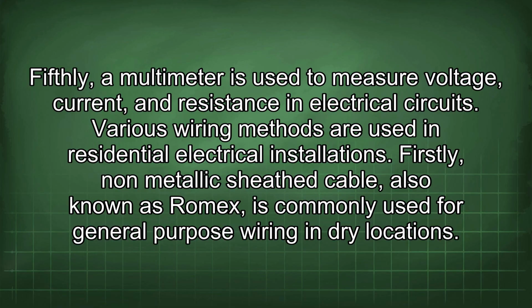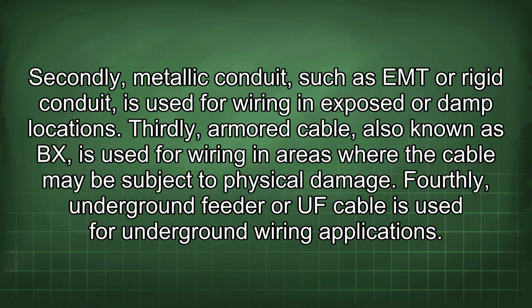Firstly, non-metallic sheath cable, also known as Romex, is commonly used for general purpose wiring in dry locations. Secondly, metallic conduit, such as EMT or rigid conduit, is used for wiring in exposed or damp locations. Thirdly, armored cable, also known as BX, is used for wiring in areas where the cable may be subject to physical damage. Fourthly, underground feeder or UF cable is used for underground wiring applications.